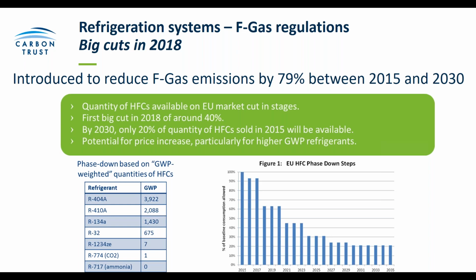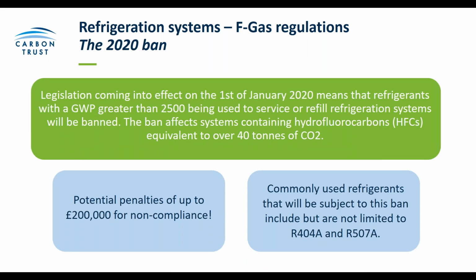The next thing to consider is that in 2020, the next big change will be coming into effect on the 1st of January of that year. Refrigerants with a global warming potential greater than 2,500 that are used to service or refill your existing refrigeration systems will be banned. The ban affects systems containing hydrofluorocarbons equivalent to 40 tons of CO2. I'll give you an idea of what that relates to in terms of the mass of refrigerant you may have in just a second. But the headline is that if you fail to comply with the regulation, you could see penalties of up to £200,000. So it's really important to make sure that you're fully aware of all the regulation and legislation going on with refrigerants.